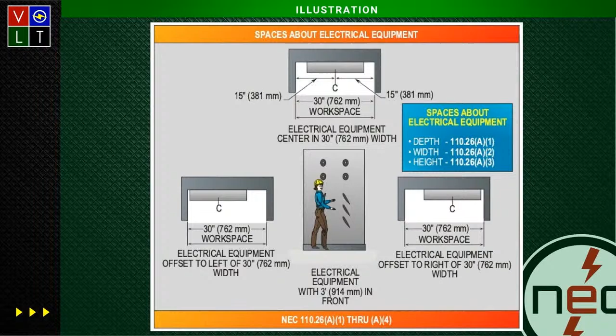These spaces about electrical equipment per 110.26A tell you this is equipment you're likely to work on while it's energized. If I'm looking for the depth of the equipment, I'm in 110.26A1. If I'm looking at the width, I'm in 110.26A2. And if I want the height, I'm in 110.26A3. We put those in there so you can follow what's happening here.